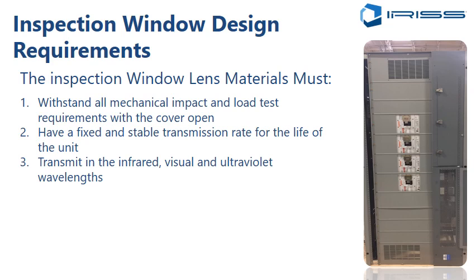They need to transmit infrared energy and also be using the visual and ultraviolet wavelengths. UV cameras are being used more and more, becoming very popular in more of the medium to high voltage systems. Above 2 kV, you can start to see a phenomenon called corona. So ultraviolet cameras, again, you may not be using them now, but you might be using them in 3, 4, 5 years time on your medium and high voltage switchgear. So you want to make sure your system can enable that.